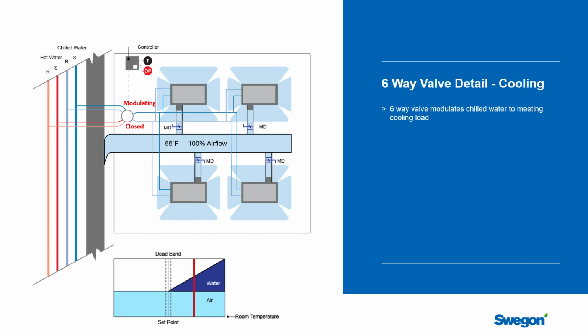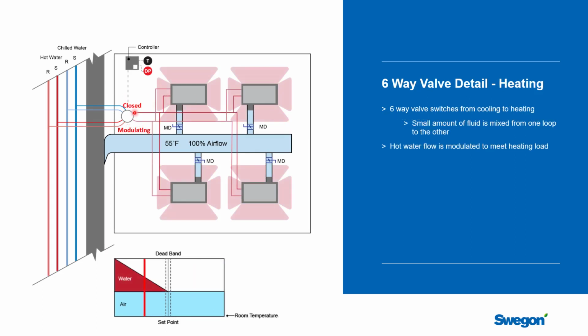Now, we go back the other way and we switch over. We close off the loop to the chilled water. Remember that when that happened, all that piping had been filled with chilled water. The coils were filled with chilled water. And so when we switched over, all of that flushed out and went back into the heating system. So you are going to move water from one loop to the other. That's just part of a six-way design. But once that's done, we're going to allow hot water to come in here and warm this air up and meet the heating load in the space, and so we can modulate that.